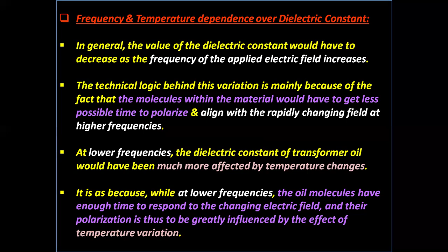At lower frequencies, the dielectric constant of transformer oil is much more affected by temperature changes. This is because at lower frequencies, the oil molecules have enough time to respond to the changing electric field, and their polarization is thus greatly influenced by temperature variation.